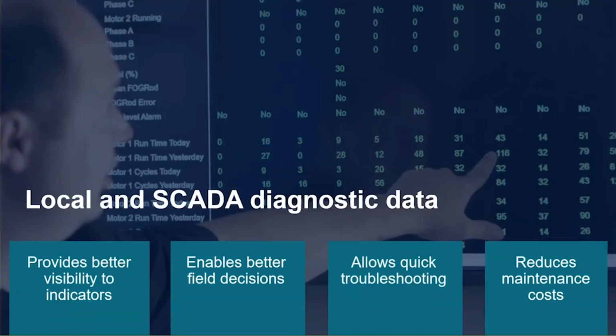It also allows you to take that information that's time-stamped to the millisecond and trust it to really do some neat things about predicting flows in your system, because everything's time-stamped to the millisecond. Even if the communication lags, you can write some software to coordinate from one location to the next. Hey, we just started up here at this exact millisecond. You're going to see flow at this other station at this exact time, based on some algorithms we have in the controller.